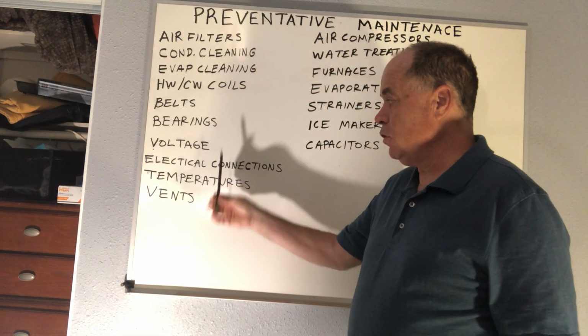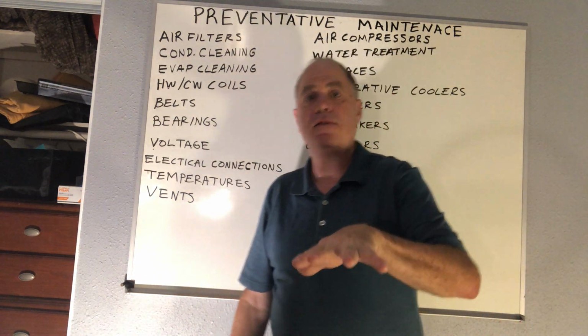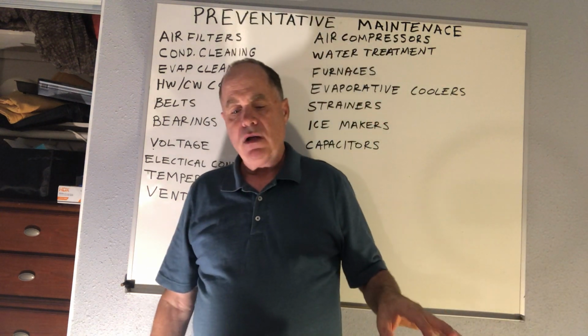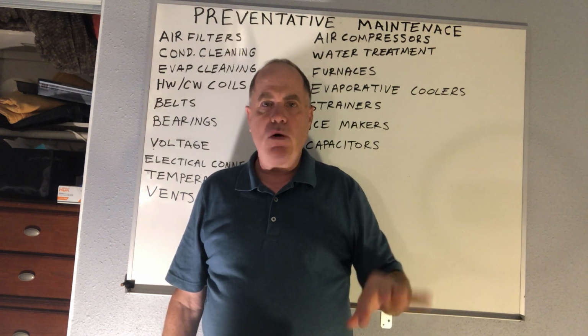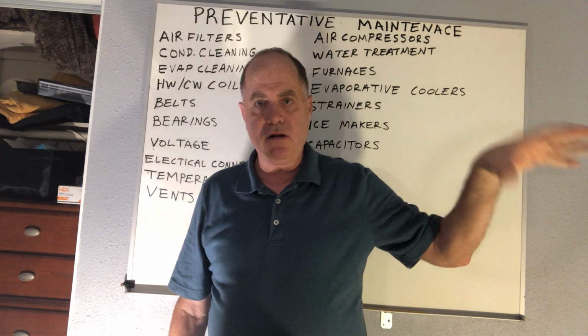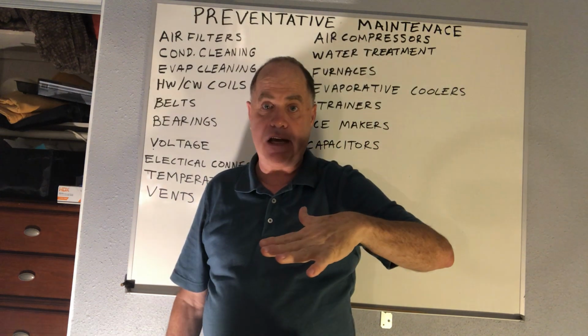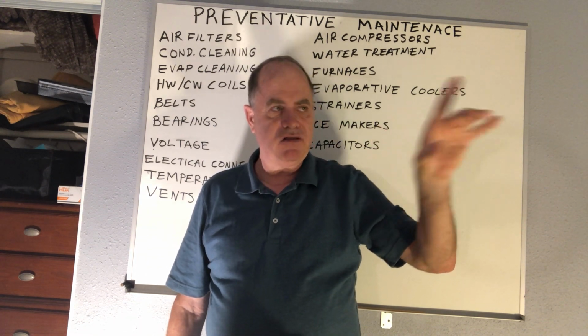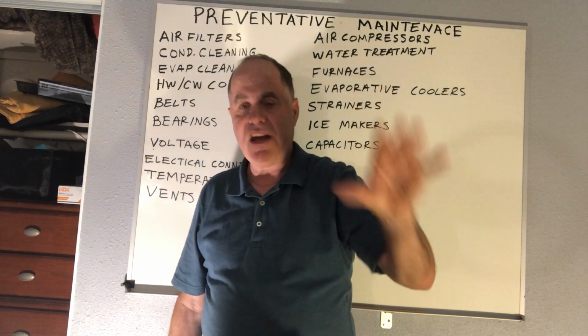Okay? Checking voltage, making sure you have adequate voltage at your equipment. We generally have a problem with low voltage. We almost never have a problem with high voltage. The only time we really do is now, actually here in 2020, and going forward. Sometimes if somebody in your neighborhood, or even in commercial, industrial, whatever, has solar panels and they're feeding back into the panel, you might get a little bit of high voltage because of somebody's solar panel nearby. Just be aware of that anomaly. Very rare, but we've had it happen.